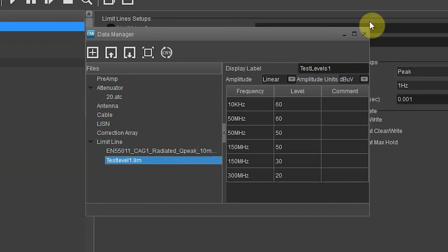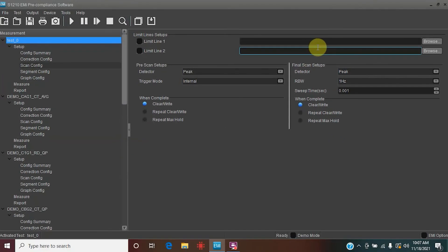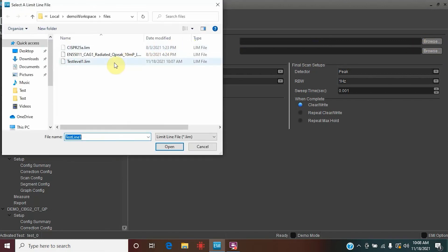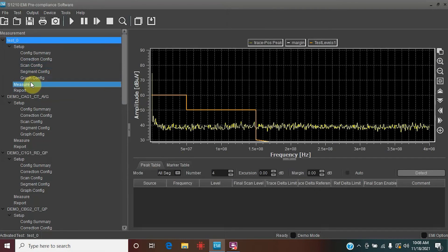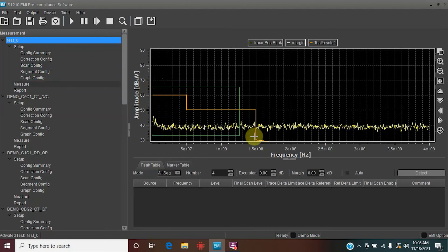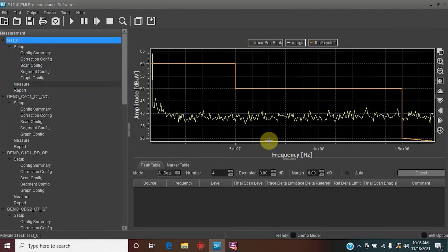Let's take one more look — excellent. Click the X and go to Browse for limit line one. Here you'll find 'Test Level One'. Open it and it did pull in. Check that box. Let's go to Measure and take a look at our line. You will see we're losing a little bit of it because the amplitude doesn't quite go down to 20, but this gives you the idea. You can see we start at 60, go down to 50, and then eventually go to 30.